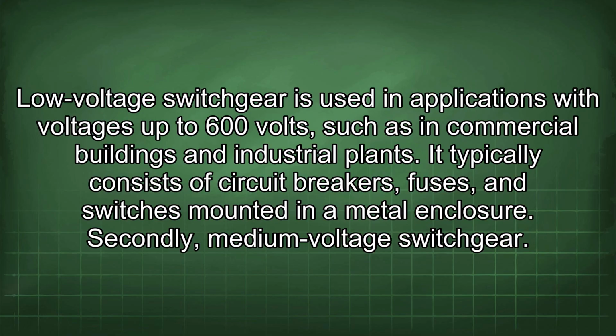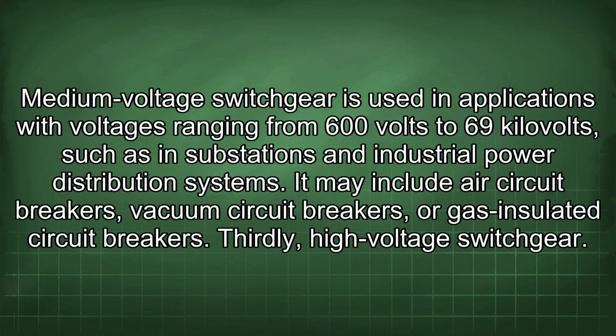It typically consists of circuit breakers, fuses, and switches mounted in a metal enclosure. Secondly, medium-voltage switchgear. Medium-voltage switchgear is used in applications with voltages ranging from 600 volts to 69 kilovolts, such as in substations and industrial power distribution systems. It may include air circuit breakers, vacuum circuit breakers, or gas-insulated circuit breakers.